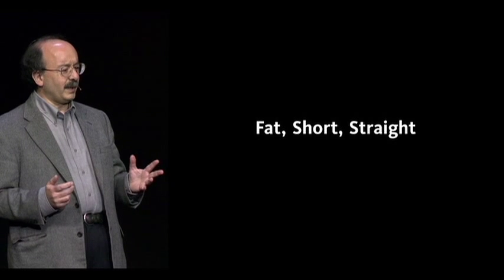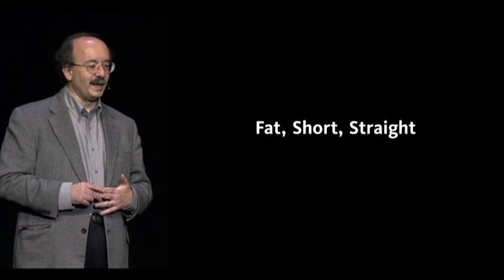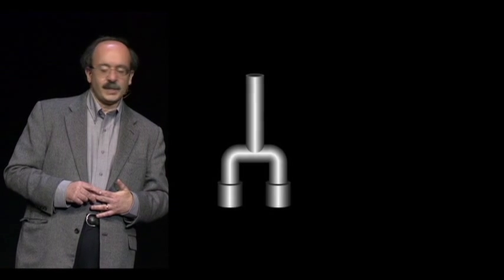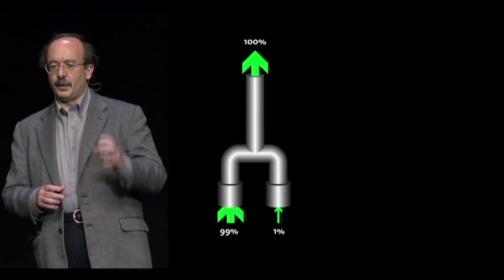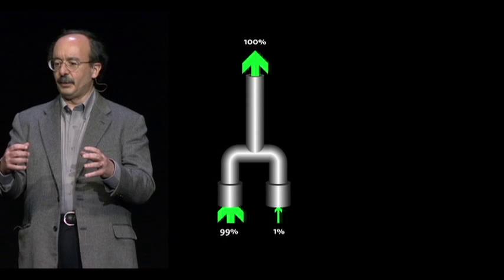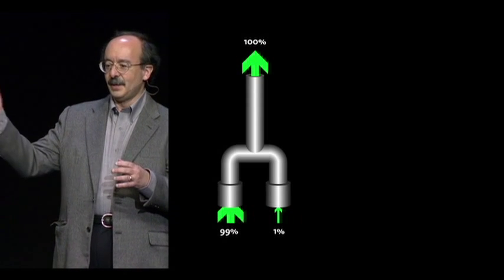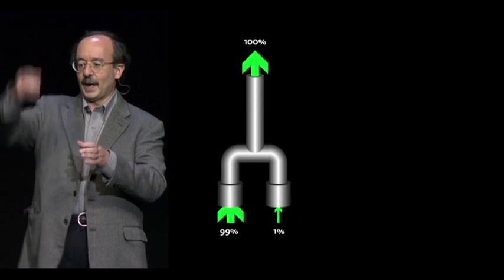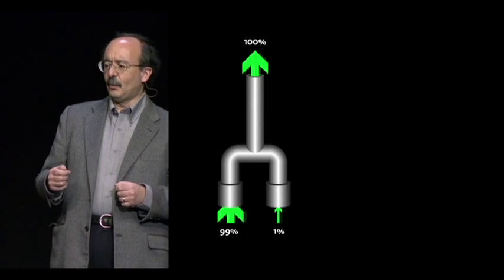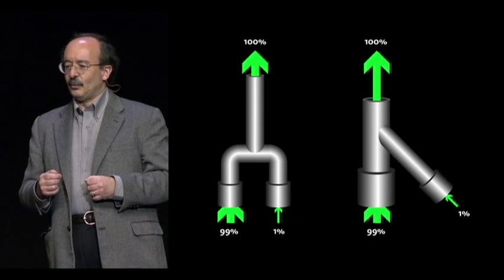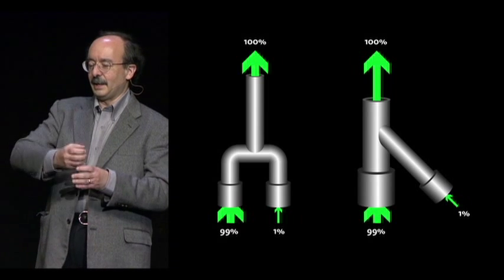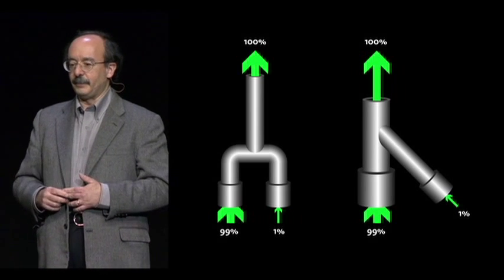This isn't very complicated, it's just good old Victorian engineering. For example, normally if we have a critical pump next to an identical in-place spare pump, we'd lay it out like this, so the flow always has to go through two right angle bends. That means friction. Why not lay them out instead with no bends for the main flow to go through, and probably fewer valves?